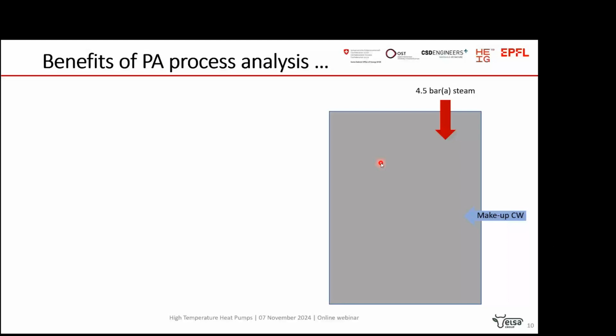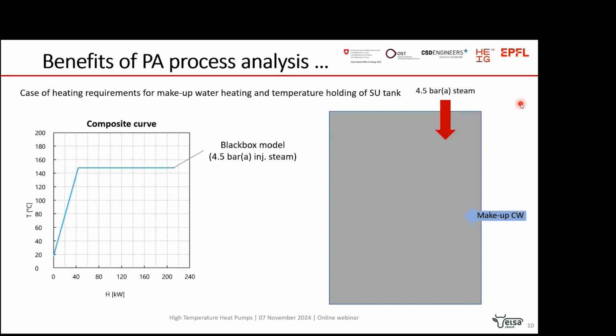We mentioned the pinch analysis as a tool to check the integration, to optimize the integration of the heat pump. I just want to show that if we consider at first the process as a black box, we see that we need steam at 4.5 bar absolute, and makeup water which comes in cool. And so what we see as a heat requirement versus temperature is that we have water that must be heated and evaporated to produce the steam that the CIP station will consume.